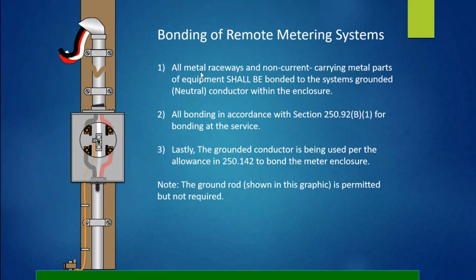Now, all metal raceways and non-current-carrying metal parts of the equipment shall be bonded together to the system grounded neutral conductor within the enclosure. We've done that here. All bonding is in accordance with section 250.92(B)(1) for bonding at the service. So we've bonded everything together. Lastly, the grounded conductor is being used per the allowance in 250.142 to bond the meter enclosure, as you see right here.